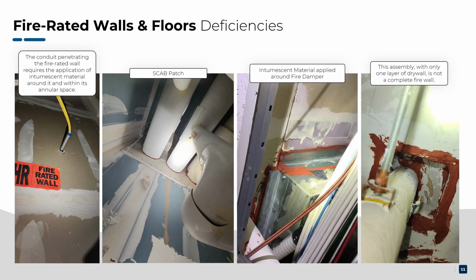Correct. And it's not just any product that will do. It has to be an approved material that's been properly tested for fire-rated assemblies. Is that a scab patch? Yes, it is, and that's not an approved repair for fire-rated walls. And what about the intumescent material around the fire damper? That makes me wonder, could it interfere with the damper during a fire? Exactly. As the material expands, it could potentially bend the metal duct housing the damper, preventing it from closing properly. And the last picture, it looks like there's enough fire-stopping material.